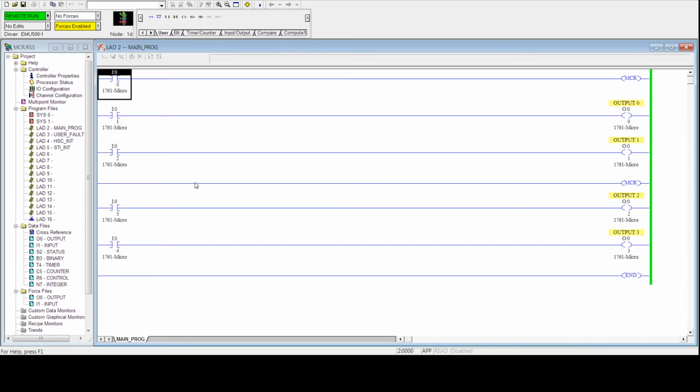Okay, so what I have built here is a very simple program. It has a couple of inputs, and they all control different lines of code, except this one up here. This one controls a MCR, Master Control Relay. And you'll notice that there's another Master Control Relay down here, and nothing's actually turning this one on or off, right? So, while the Master Control Relay is on, it's going to let the outputs of these be energized. See? The outputs are energized, just as normal.